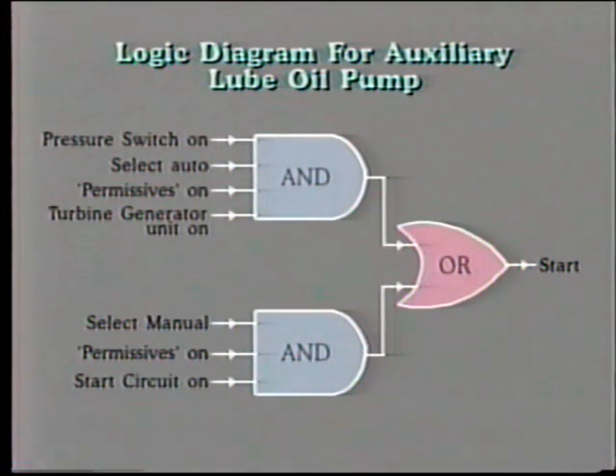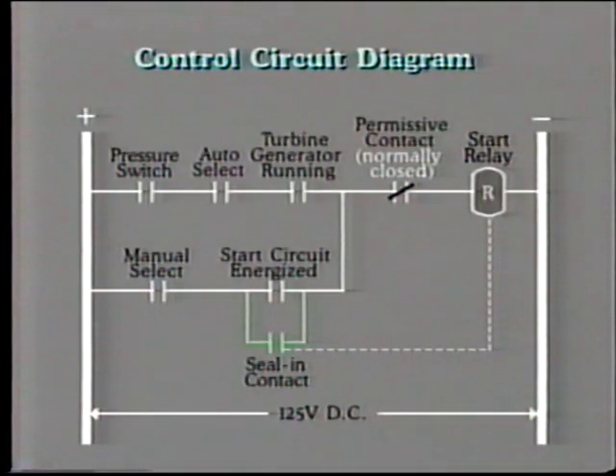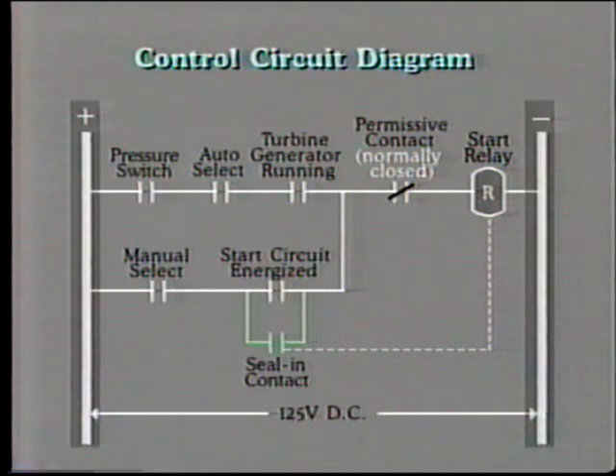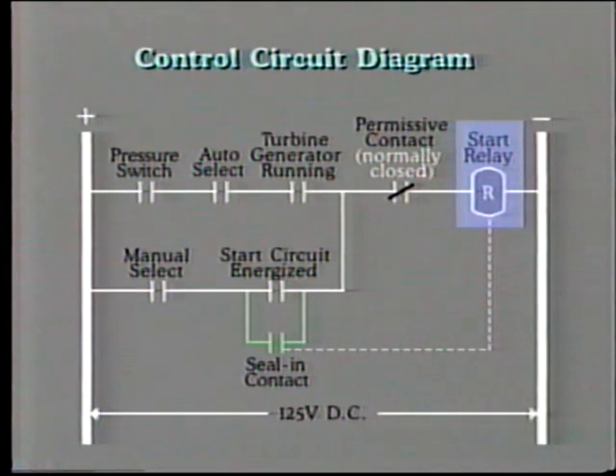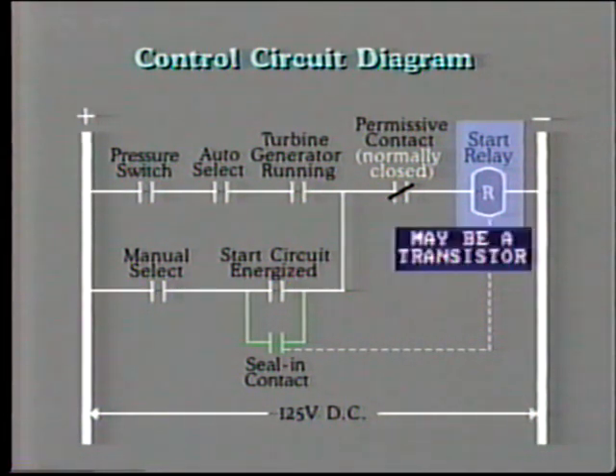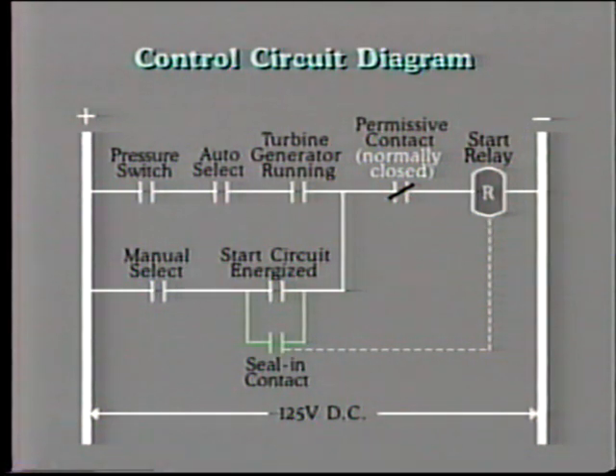Now, if we were to draw this logic as an electric control circuit diagram, it would probably look like this. Here we have our DC bus available to energize the auxiliary oil pump starting relay. This is shown as a relay here, but in many control circuits it may be replaced by a transistor. To start the pump automatically, the following contacts must be closed. The turbine must be running with the on contact closed. The auto manual selector switch must be on auto, and the pressure switch must be closed due to low oil pressure.